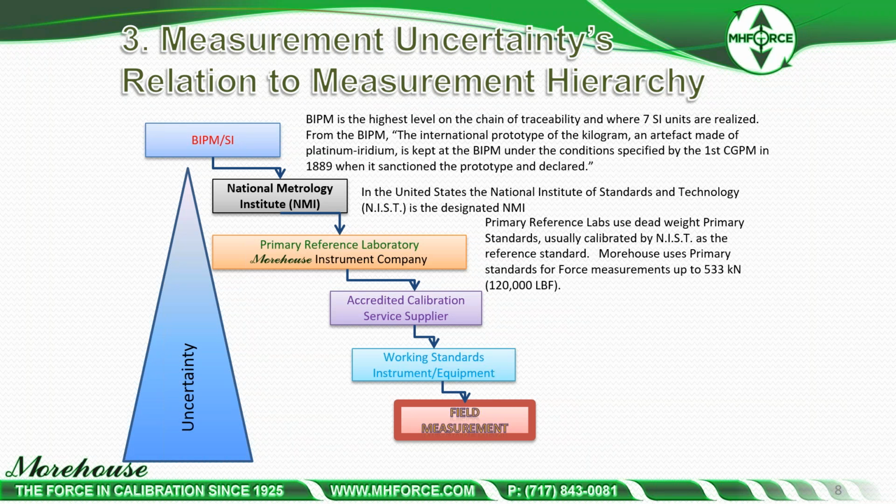The United States Air Force, the United States Army, and some other primary reference laboratories have this same type of capability. And then we go down from there to the accredited calibration suppliers. They use secondary standards, those calibrated by primary.